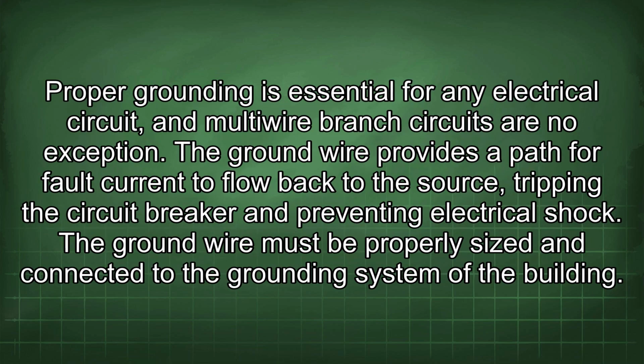Proper grounding is essential for any electrical circuit, and multi-wire branch circuits are no exception. The ground wire provides a path for fault current to flow back to the source, tripping the circuit breaker and preventing electrical shock. The ground wire must be properly sized and connected to the grounding system of the building.